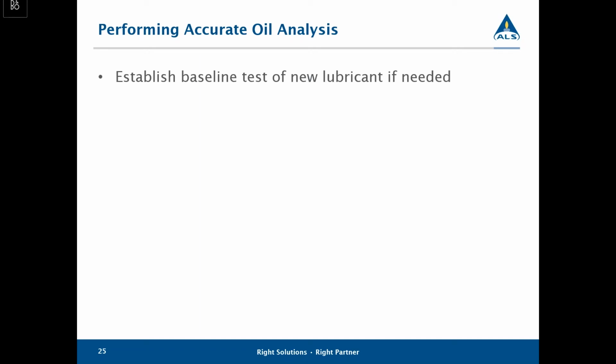To perform accurate oil analysis, it's important to establish a baseline of new lubricant if needed. It's not always needed because a lot of times we'll have a baseline of that new oil. But if you're using a semi-exotic oil, feel free to reach out to us. We can let you know if we've tested it before. But if not, you can send us oil and we can test it.